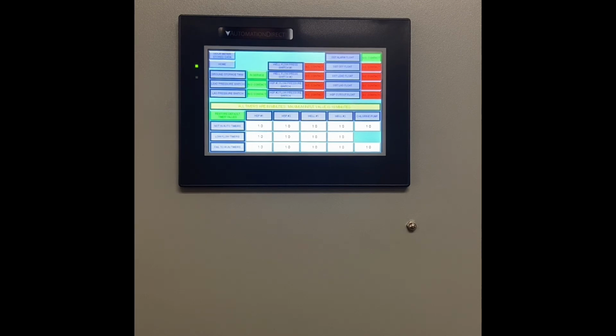It's a matter of changing the float out and then selecting the contact type that you have to match the system. So if you had a normally closed in service, it failed, and the only thing you had was a normally open, not a big deal. Put your normally open float in, come to the screen, change it over to normally open, and you're off and running. You don't need to order special floats, and you don't have to wait. That's a benefit.